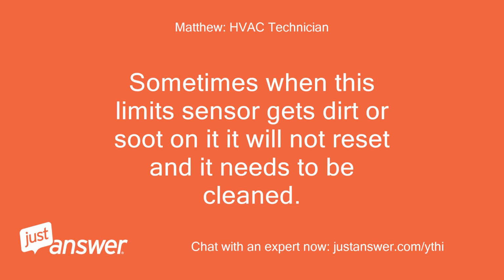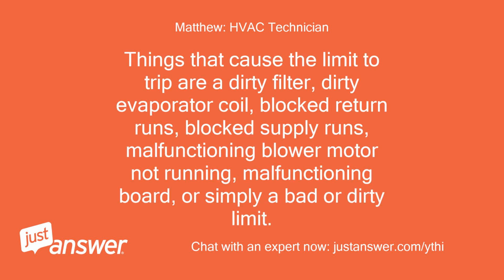Sometimes when this limit sensor gets dirt or soot on it, it will not reset and it needs to be cleaned. Things that cause the limit to trip are a dirty filter, dirty evaporator coil, blocked return runs, blocked supply runs, malfunctioning blower motor not running, malfunctioning board, or simply a bad or dirty limit.